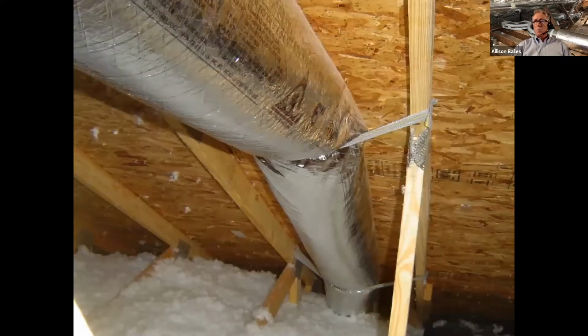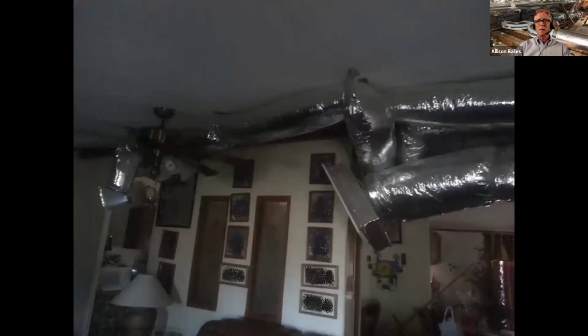In the South, dehumidification is a big thing. And one way to do dehumidification is to cool the air down, make it really, really cold, and then reheat it, the reheat system. This is a reheat system in Charleston, South Carolina. Very inexpensive reheat right here. You just staple the flex duct up right under the roof deck. Lots of reheat there. Of course, we want ducts inside the enclosure, and everybody thinks you have to use hard pipe for that, but hey, you can do it with flex duct too.